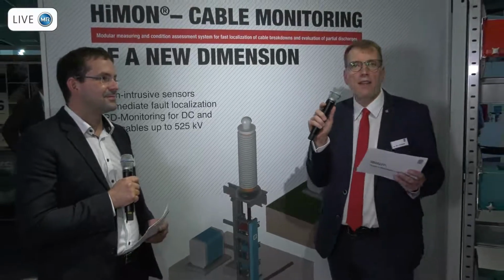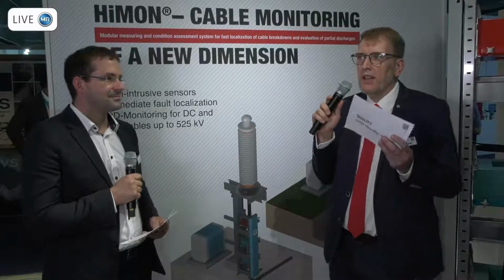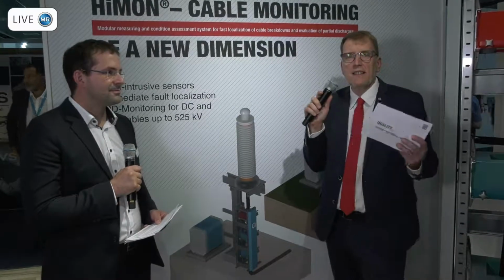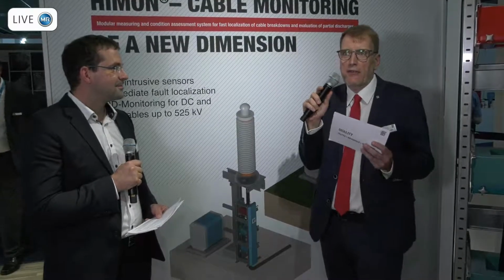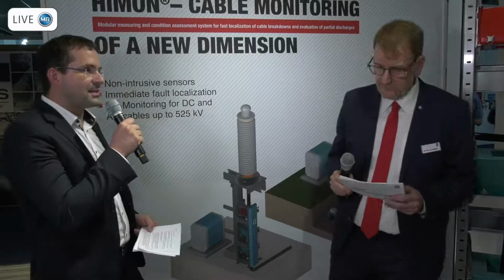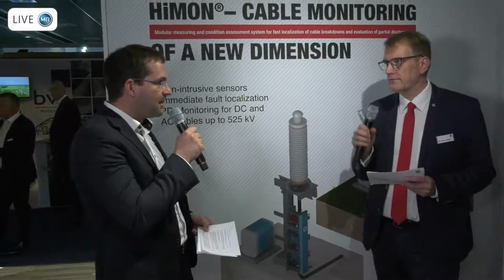So after a failure, typically you go back to the cable with the test source, and then you try to apply high voltage again, and then you have a breakdown of the residual resistance, and with this traveling wave, you can then identify the failure. So what is the system doing differently? You're absolutely right, Uwe. What you described is time domain reflectometry. That means the method behind. That's the correct wording.